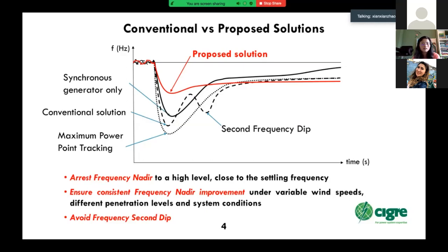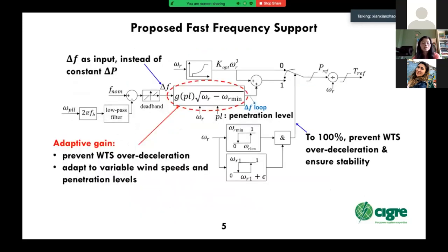In the proposed solution, an adaptive gain is used to ensure consistent frequency nadir improvement under variable wind speeds, different penetration levels and system conditions. This slide shows the details of the proposed fast frequency support control. The adaptive gain is a function of the real-time rotor speed, the minimum rotor speed and the penetration level. Using a proper function, the adaptive gain first can prevent wind turbine system over-deceleration and ensure the wind turbine system stability.